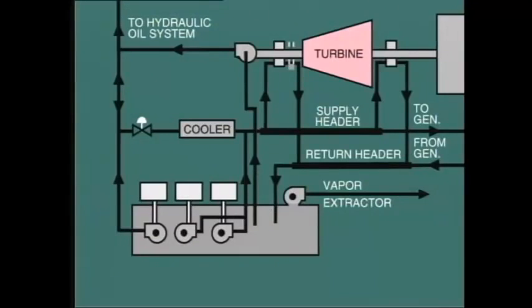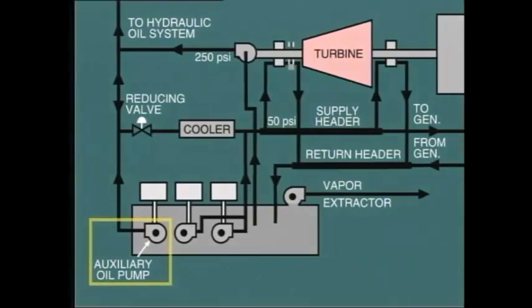Diagrammatically, the scheme looks like this. When the machine is in operation, the main oil pump here delivers oil at 250 psi. This supplies the hydraulic oil system. At the same time, it provides oil to the lube oil header at 50 psi through a reducing valve. During startup and shutdown, a motor-driven high-pressure oil pump is used. Again, this supplies both the hydraulic oil system and the lube oil system. In this arrangement, this pump is known as the auxiliary oil pump, since it is the main standby to the shaft-driven pump.